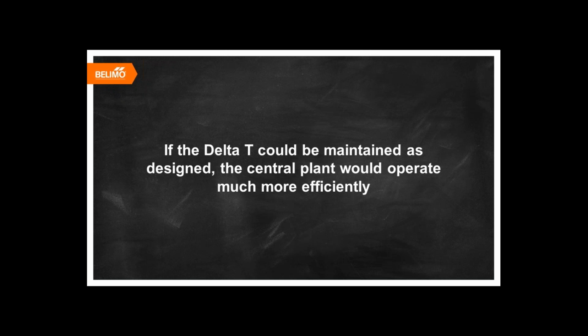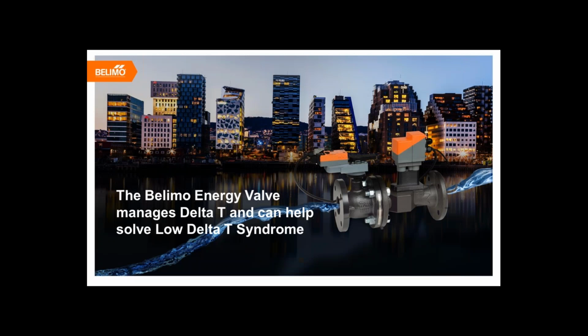With those examples in mind, we can conclude that if the delta T could be maintained as designed, the central plant would operate much more efficiently. I'm going to show you a product that you can use to enact this. The Belimo Energy Valve manages delta T and can help solve low delta T syndrome. The Energy Valve, through its delta T manager software, can be set to maintain a desired delta T set point. It has a built-in flow meter and two temperature sensors to monitor and maintain flow.